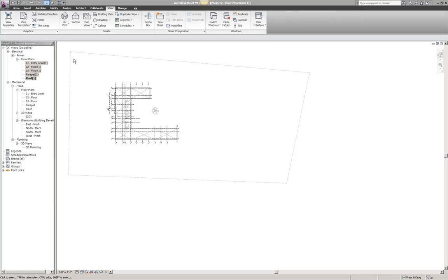So one of the common questions that we get from end users when it comes to creating views in Revit MEP is they apply the view template for electrical lighting, for example, if they want to set up their lighting views, but typically they need to see the ceiling in the architectural model to host their fixtures to. But a lot of times they'll apply the view template, but they still don't see the ceiling. It's usually because they may overlook the setting that's unique to Revit MEP in visibility and graphics for reflected ceiling plan. It's called Underlay Orientation.